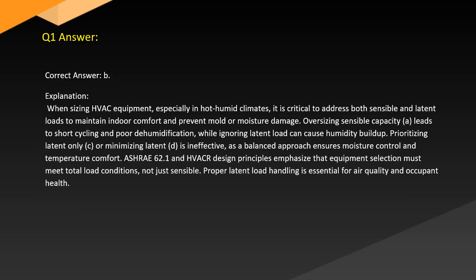Answer. Correct answer: B. Explanation. When sizing HVAC equipment, especially in hot, humid climates, it is critical to address both sensible and latent loads to maintain indoor comfort and prevent mold or moisture damage. Oversizing sensible capacity (A) leads to short cycling and poor dehumidification, while ignoring latent load can cause humidity buildup. Prioritizing latent only (C) or minimizing latent (D) is ineffective, as a balanced approach ensures moisture control and temperature comfort. ASHRAE 62.1 and HVACR design principles emphasize that equipment selection must meet total load conditions, not just sensible. Proper latent load handling is essential for air quality and occupant health.